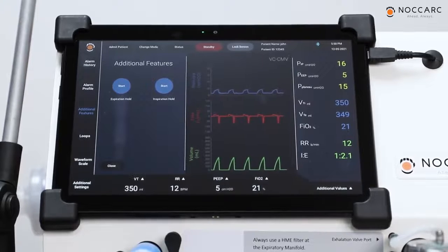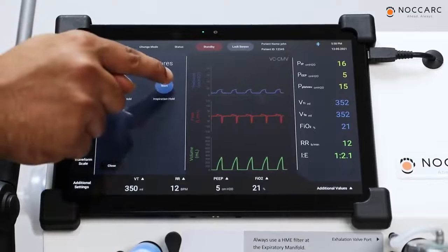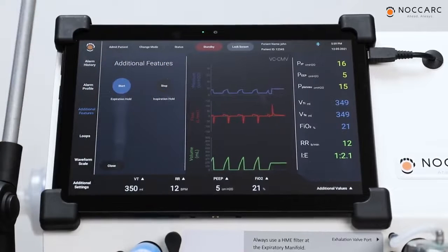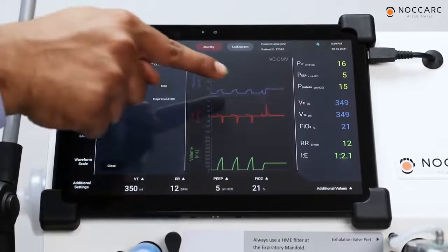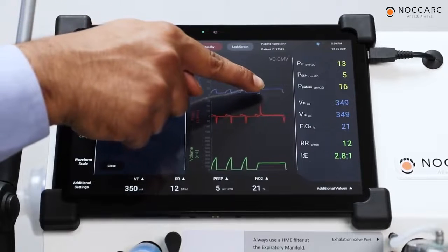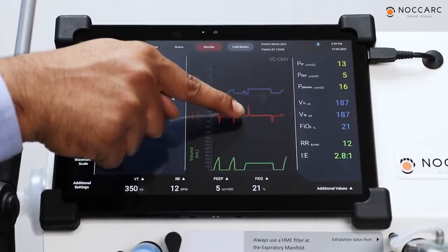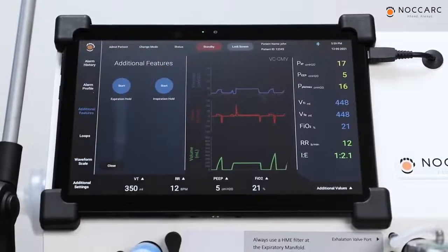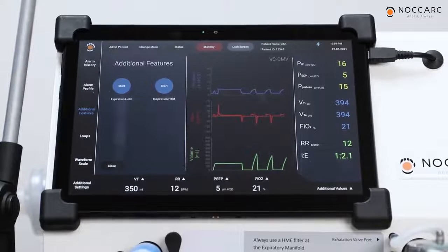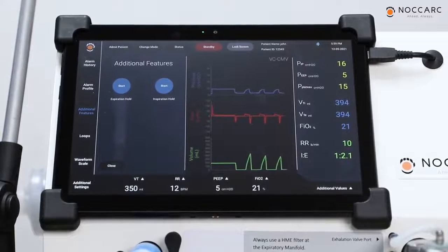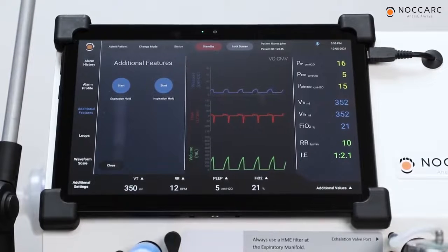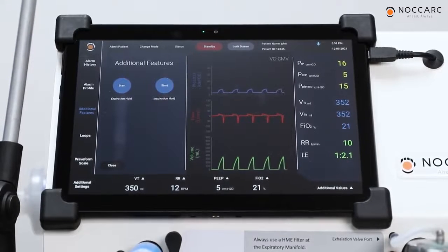To perform an inspiratory hold, we need to press on this inspiration hold. In the graph section, here you can see inspiration hold has been performed. And in the flow graph, here you can see there is a no flow state during inspiration hold. Inspiration hold will be stopped automatically after 10 seconds. Now we will see expiration hold.